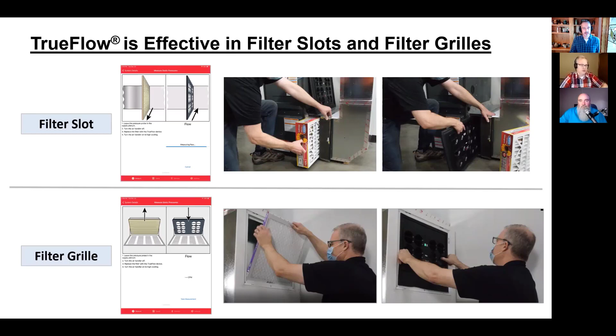That's why we take the static pressure measurement in the supply plenum while you do the swap, because we'll be able to look at before, with the filter, and after, with the TrueFlow. We make a correction because we're essentially calibrating your system with the filter in it and then comparing that with the TrueFlow to make that correction.